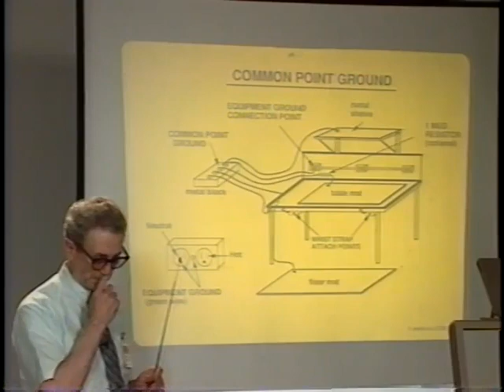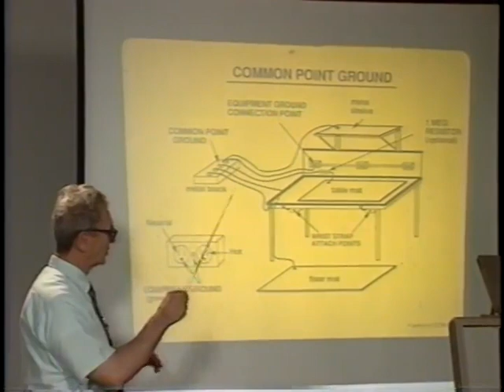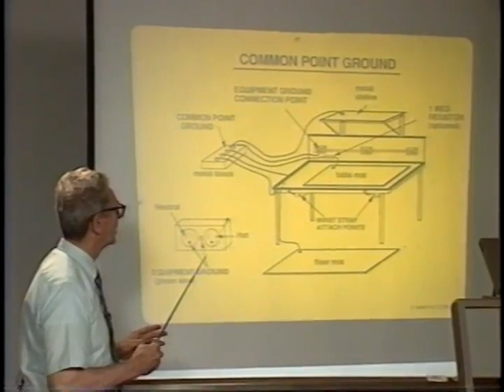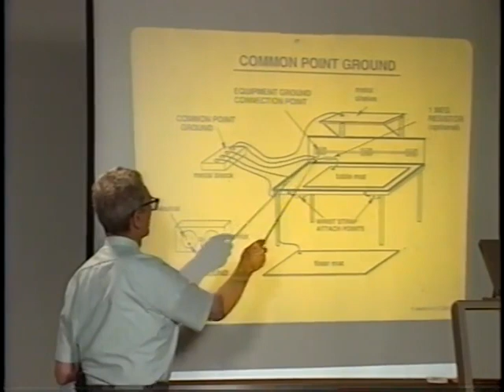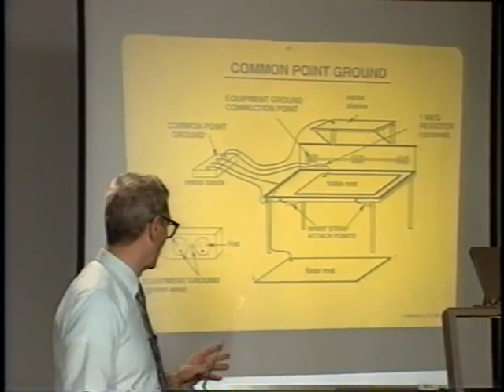The wrist strap connections here go to this point, and all that is connected to the equipment grounding conductor, which is connected to the building. The floor mat here is connected to that point. The only thing that isn't connected is the ESD floor, which is connected to the equipment grounding conductor through the building connection. This equipment grounding conductor is at the same potential as the building ground, and therefore you do not have potential differences between any of these objects or pieces of equipment if they're all connected up and certified.